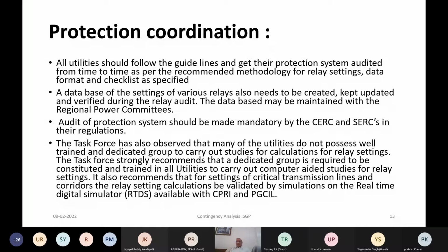In the numerical relay, many times, being digitally programmed, all the settings... So many times during testing or any other commissioning activity, or some modifications being carried out by the OEMs of the protection suppliers, some changes in the settings are not restored back after testing is completed, and this results in certain undesirable operations. And to control such a thing, this audit will actually help.